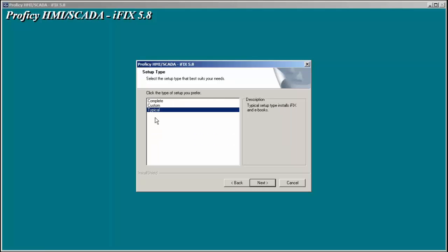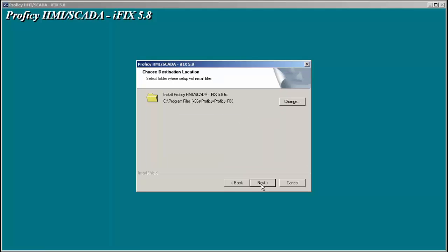In general, we do a typical install. You could choose complete, custom, but we will in general suggest a typical install. We also suggest installing iFix into the default destination directory, which on a 64-bit machine is program files x86, Proficy, and Proficy iFix. You can always change the location of your picture files or database files later on, but it is suggested that the default install is done to the suggested directory.